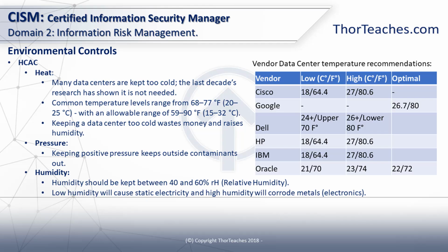A little bit of a sidetrack, but now you understand how it's important to keep the pressure slightly higher so we can keep the contaminants from the outside, well, out. We've touched on the humidity before. It should be kept somewhere between 40 and 60% relative humidity.